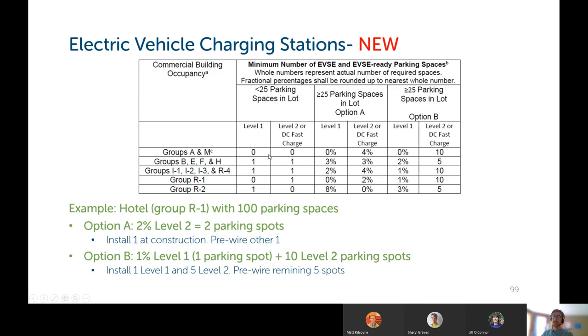Again, the code says you only need to install half of those and then pre-wire the remaining half. And that's also the case if you're over 25 parking spaces in your lot, where you've got two different options. An example I'm going to use is a hotel, which is group R1, with 100 parking spaces. So you've got two options here for over 25 parking spaces, A and B, group R1. The first option, you would not need any Level 1 chargers, but you would need 2% of the spaces to have Level 2 chargers. So 2% of 100 is 2 total parking spots.